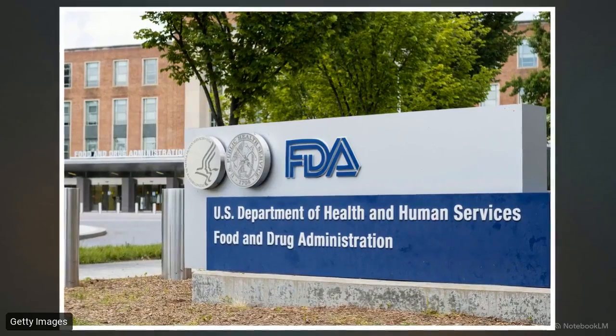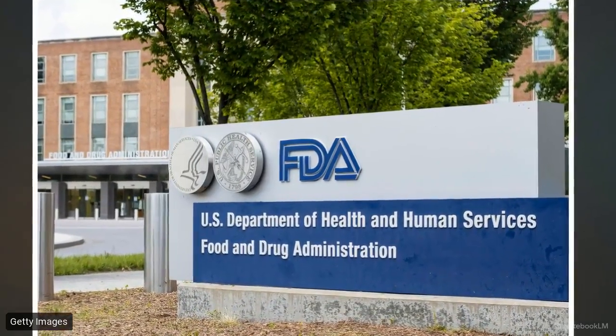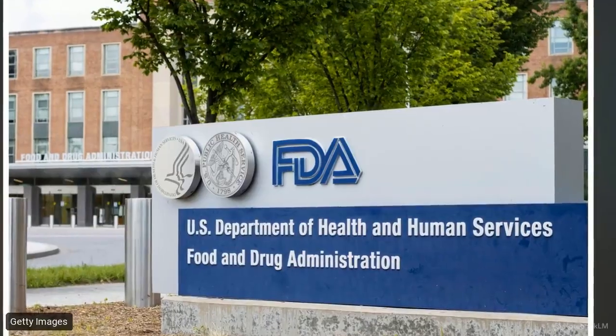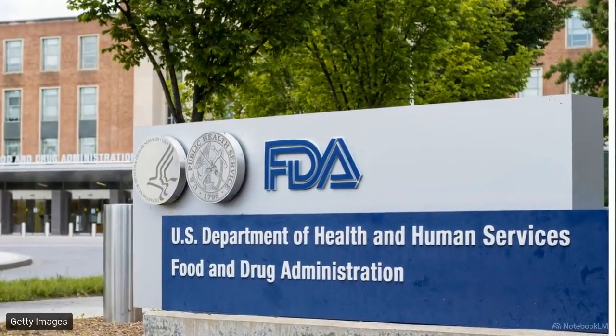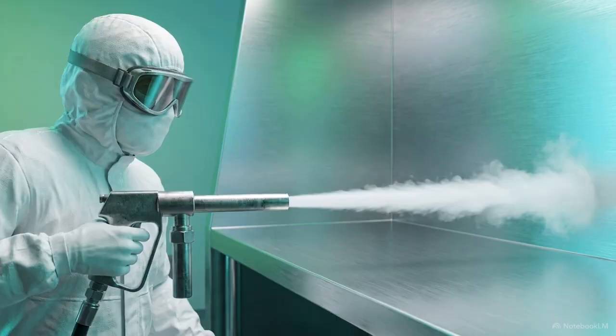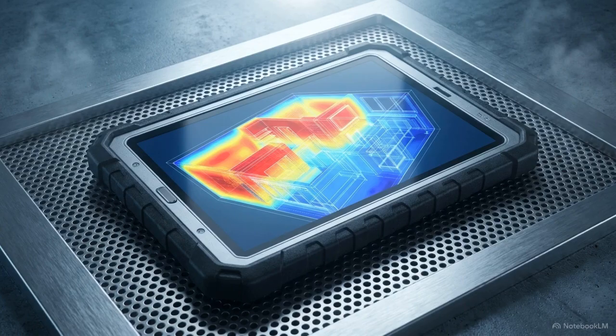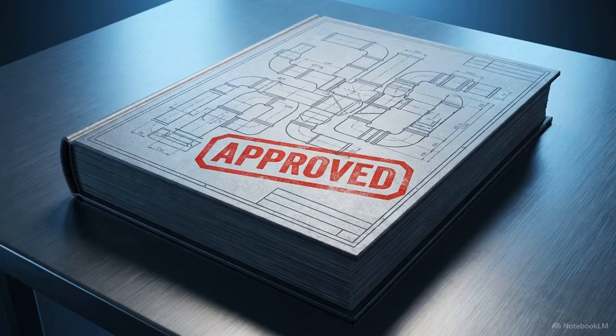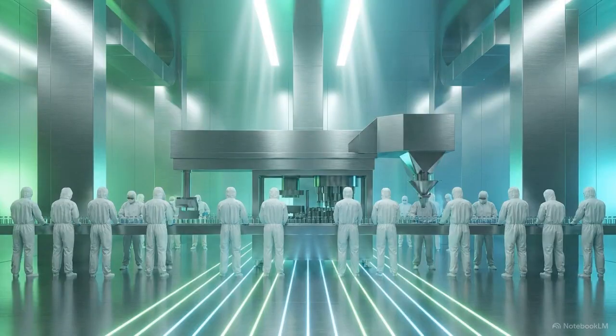However, a theoretical HVAC design is useless to regulatory agencies like the FDA without physical GMP validation. Regulators demand hard physical proof. This means conducting airflow pattern smoke tests, verifying HEPA filter integrity, and performing exhaustive spatial mapping for temperature and humidity. Strict validation is the bridge between engineering theory and regulatory reality. It is the mandatory step that transforms a functional room into a legally compliant pharmaceutical environment.